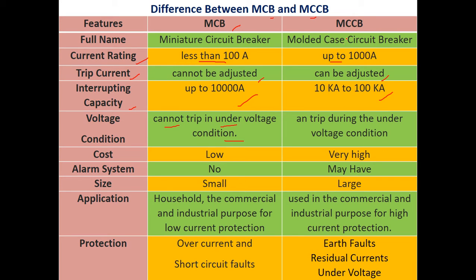Under voltage trip conditions: under-voltage tripping cannot be done with MCB, whereas MCCB can trip during under-voltage conditions. Regarding cost, MCB is cheaper compared to MCCB, which is very expensive in comparison. For the alarm system, there is no alarm system available with MCB; however, with newer versions of MCCB, an alarm system may be included.